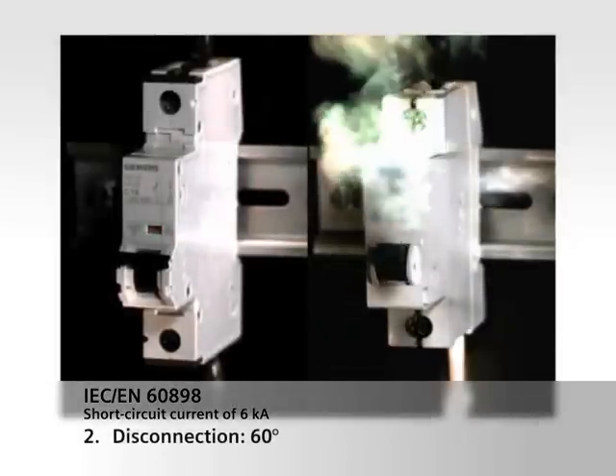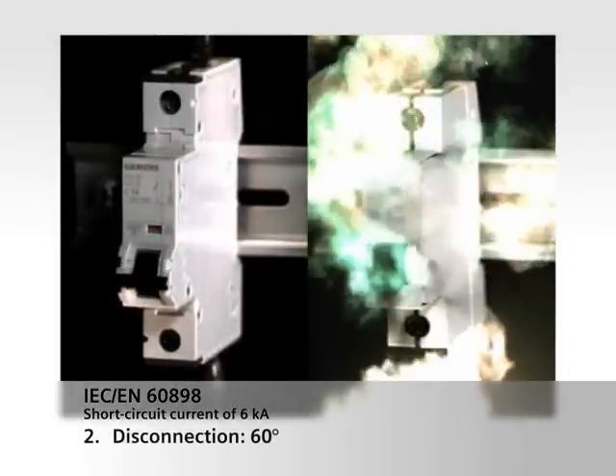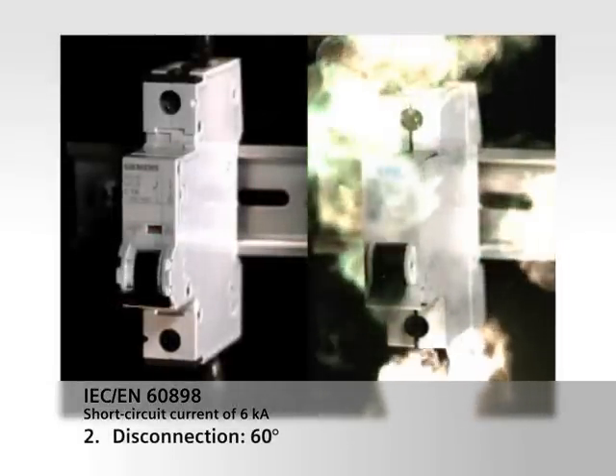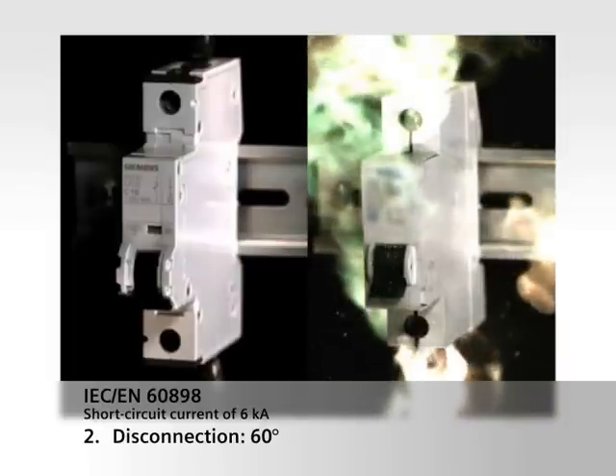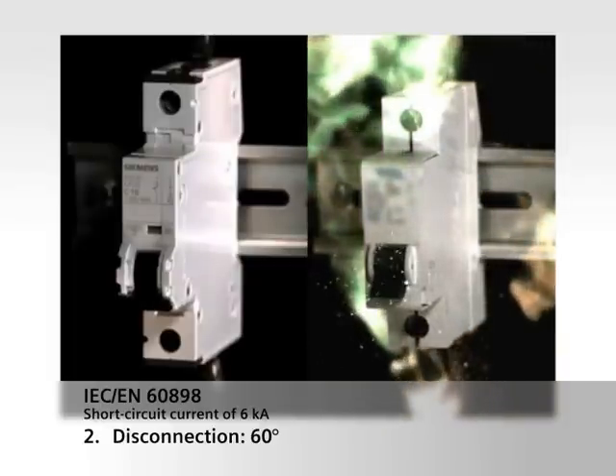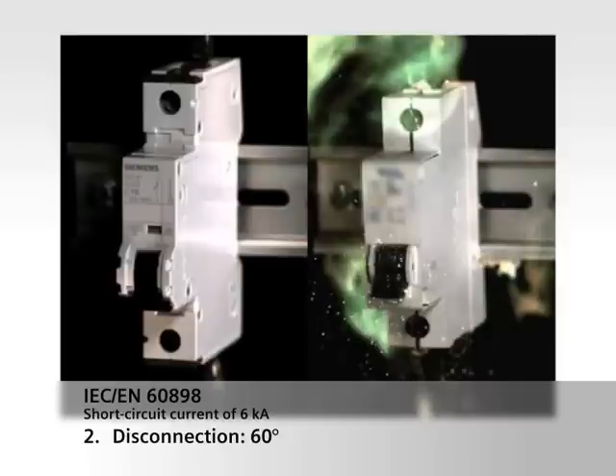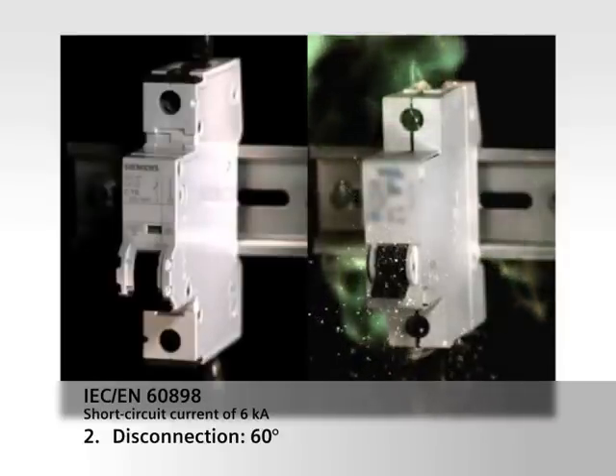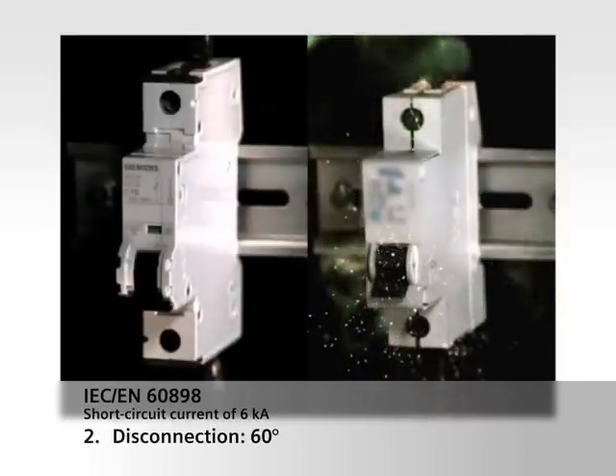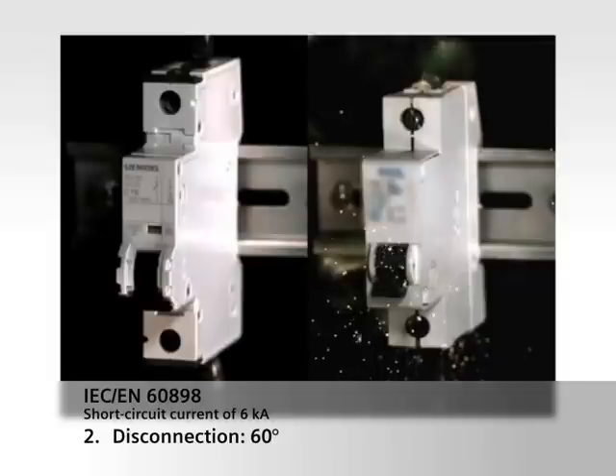As was the case with the first disconnection, the miniature circuit breaker from Siemens trips extremely quickly and safely. But the flames being emitted from the other device increase considerably. The sparks flying around can cause not only huge problems and damage to the plant, but also result in personal injury to operating personnel.